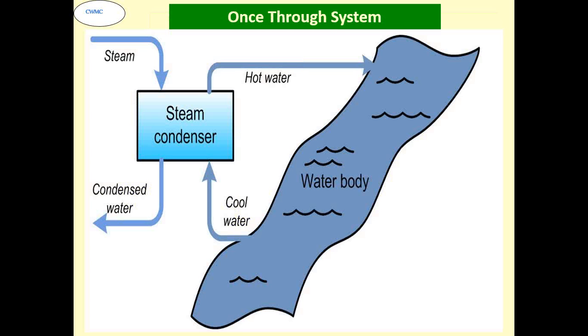Now typically, there are three types of cooling water systems. The simplest is the once-through system, where we take the cooling water from a source, maybe a river, maybe a lake, pass it to the steam condenser, and then the hot water is sent back to the main water body. That's one of the simplest systems. But today, as per environmental regulations, at least in India, not more than a 5 degree temperature rise can be there from the input to the output water going to the water source. Which means most of the new plants will come with a cooling tower, because a cooling step will necessarily be required before the water is passed on to the water body.